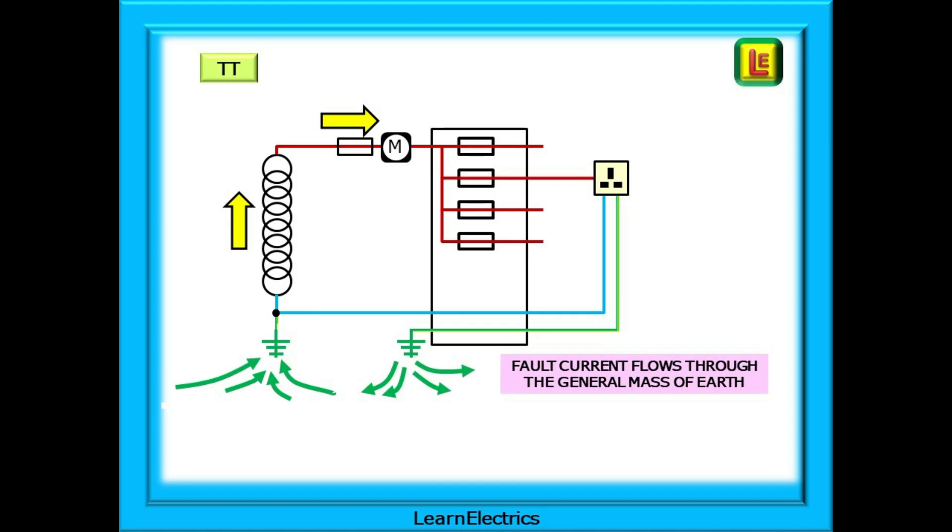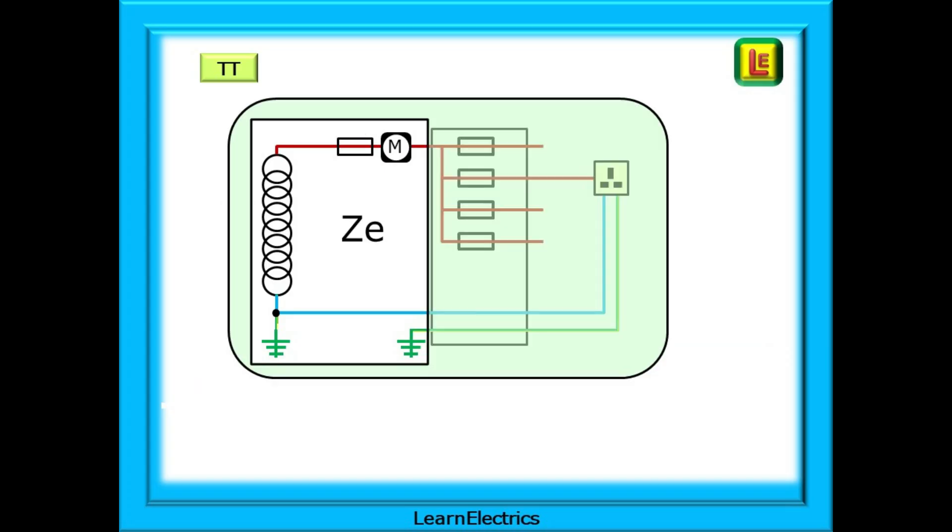And this is always the difficulty with TT systems. Because the current flow into the Earth is low and slow, it is often impossible to get enough fault current flowing to make overcurrent protective devices operate, and this is covered in an earlier video. Again, the ZE part of the TT system is shown here. Similar, but be aware of the difference to the TNS and TNCS systems.